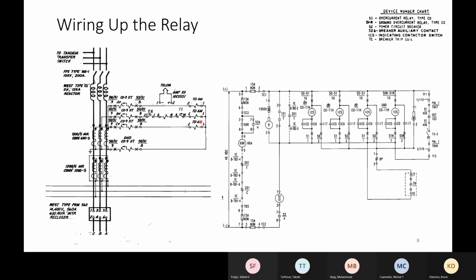And then remember back from the symmetrical components portion of the class, if I sum my 3 phases together, what do I get? I sum A, B, and C, and they're balanced. How much current flows in my ground? 0. Right. So typically there's 0 current flowing back to here. But I do put a ground relay there. It's normally going to be measuring 0 for balanced 3-phase faults. These relays have to be set above load. I can set this one pretty sensitive because I don't have to worry about load.